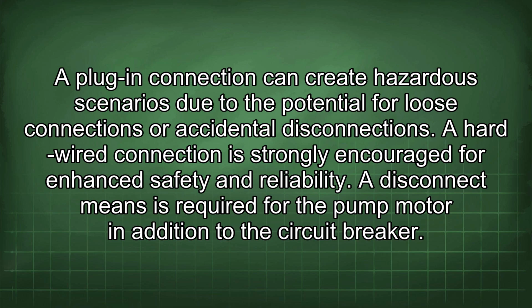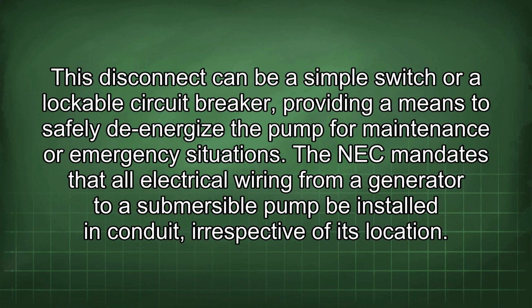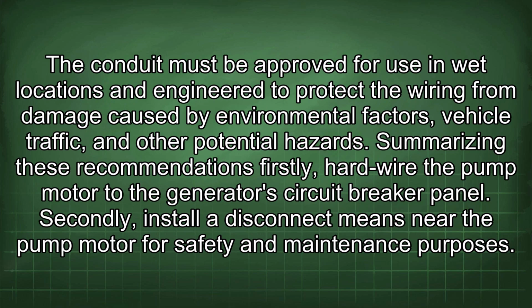A disconnect means is required for the pump motor in addition to the circuit breaker. This disconnect can be a simple switch or a lockable circuit breaker, providing a means to safely de-energize the pump for maintenance or emergency situations. The NEC mandates that all electrical wiring from a generator to a submersible pump be installed in conduit, irrespective of its location. The conduit must be approved for use in wet locations and engineered to protect the wiring from damage caused by environmental factors, vehicle traffic, and other potential hazards.